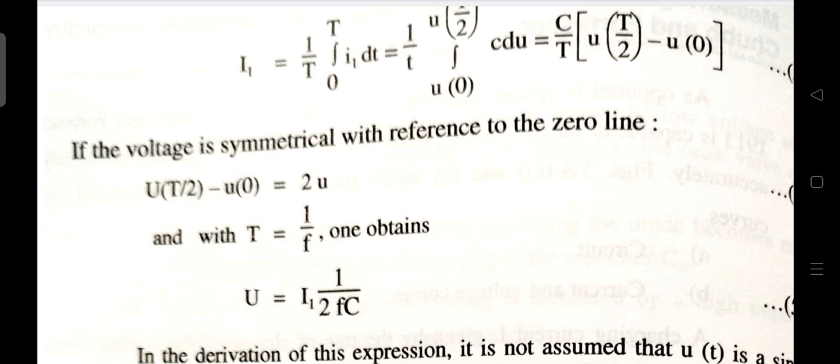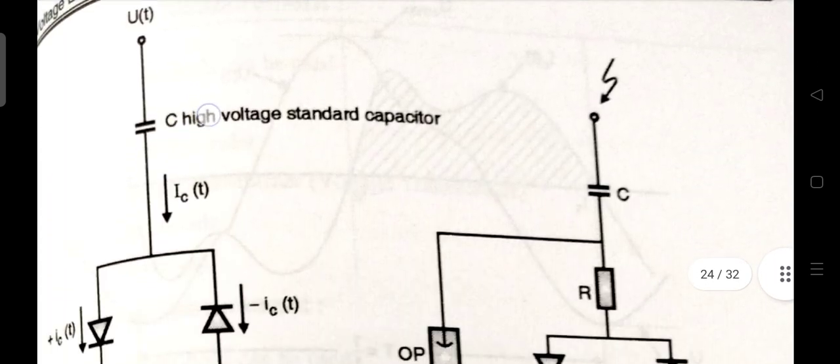But when semiconductor rectifiers are used, only one maximum per half period can occur. The use of synchronous mechanical rectifiers or controllable rectifiers allows correct measurement of AC voltage with more than one maximum per half period. Oscillograph monitoring of high voltage shape is necessary and is usually done by observing the current i1, which is allowed to have only one crossover in a half period.